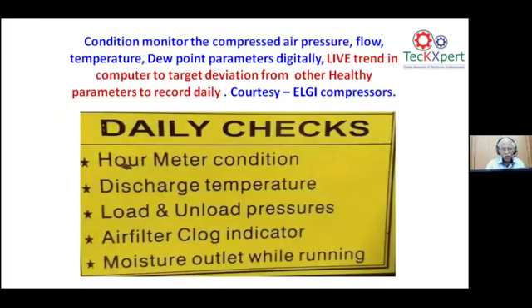So, the daily checks, thanks to the ELGI compressors, to be monitored in the existing compressed air system. One is the hour meter reading on the loading hours and unload hours. Then the discharge temperature of the compressor, as seen at the air receiver. See how the post air cooler is working; that can be seen by the air receiver's temperature. Load and unload pressures, whether we have optimized. Then the air filter clog indicator. This is a very gray area.